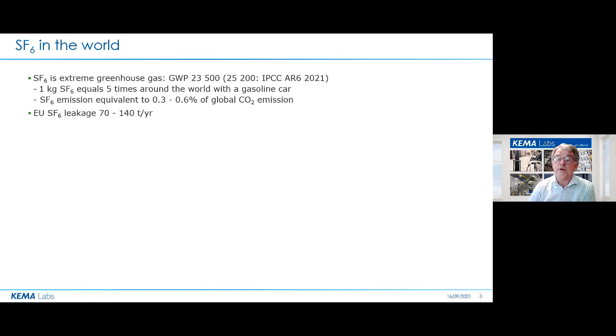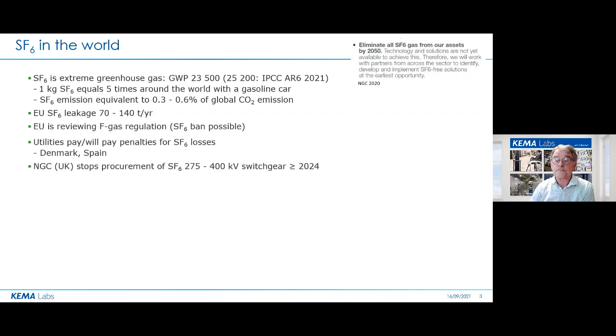The electrical industry emission in the EU is around 100 ton of SF6 gas per year. And it's clear that the EU is working on a regulation of F-gas, and taxation will be more common than it is already now. Most large TSOs have made roadmaps to reduce SF6. One case is shown here. National Grid Company of the UK will eliminate SF6 from all its assets by 2050 and stop procurement of its extra high voltage SF6 switchgear by 2024.